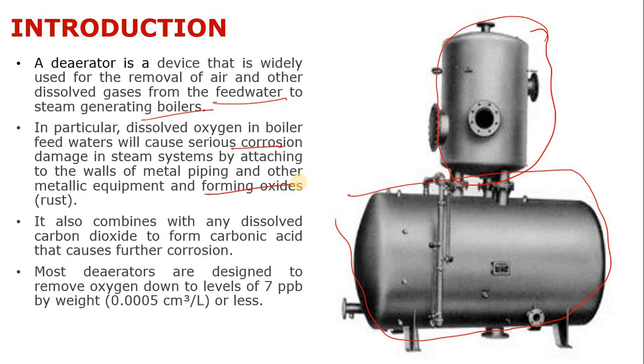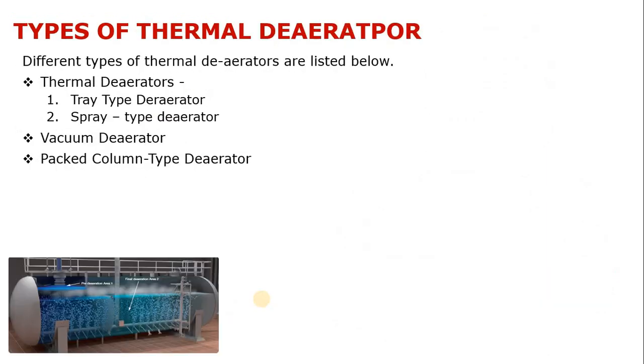When oxygen combines with dissolved carbon dioxide, carbonic acid is formed, which further leads to corrosion. Most de-aerators are designed to remove oxygen down to a level of 7 ppb by weight or less, which ensures that corrosion is minimized.